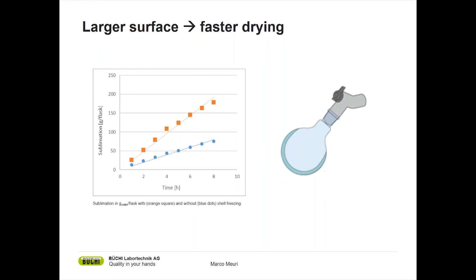If you look at the graph on the left hand side, we have the orange squares, which is a flask that's been frozen in a freezer by standing there, and we have the blue dots that have been used with... sorry, I mixed it up. It's exactly the other way around. The blue dots are frozen in a conventional way, just standing in the freezer, and the orange squares are frozen by rotational freezing. If we compare the two, we can see that shell freezing has a sublimation rate that is at least twice the sublimation rate of the conventional freezing method. This is very impressive and will allow you to freeze dry your sample much faster than if you would use conventional freezing just in a freezer.